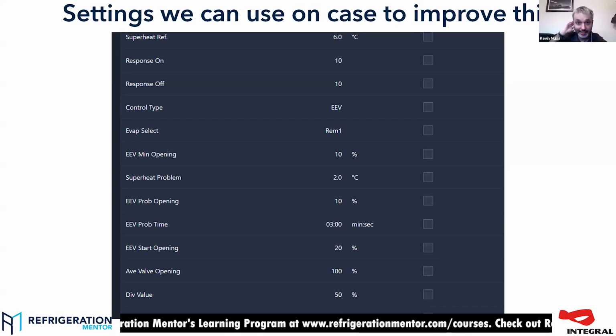Yeah, so on your case controller, the settings you can adjust for superheat control, as I mentioned, are response on and response off. On this particular example, we've set them for 10, which is at the slower end of things. And I wouldn't make it faster unless it was causing an issue. The temperature drifting up a little bit is not a major issue. Worth saying because we've got an American and European audience: in the US and Canada and what have you, I think you use a lot more setups with EPRs on the stubs.